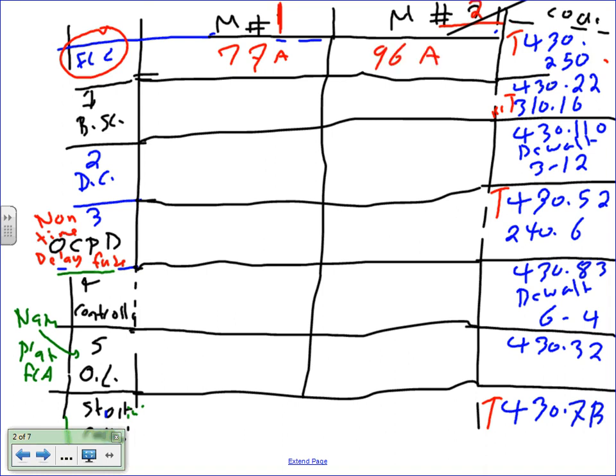Can I have a thumbs up, Chad, that we know how to go to Table 430.250 based on the voltage and the horsepower and find the full load current? Yes, no? Based on Table 430.250. Can you guys just find one of them? Make sure you know how to use the table. I have no doubt that you guys are great at finding that table. Okay, so that's basically the start point. 77 amps, as well as 96 for the two motors. Piece of cake. Piece of cake. Second thing is the disconnect.